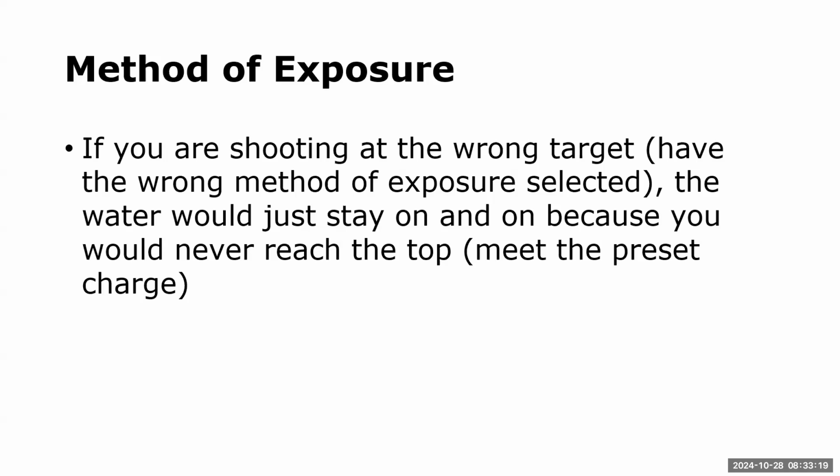That exposure is going to stay on and on and on until it hits what we call a backup exposure. And we'll talk about how big that is with most rooms these days, because we don't have the ability to set a backup time. So this patient is receiving all this radiation for nothing, right? Because these over here are waiting.